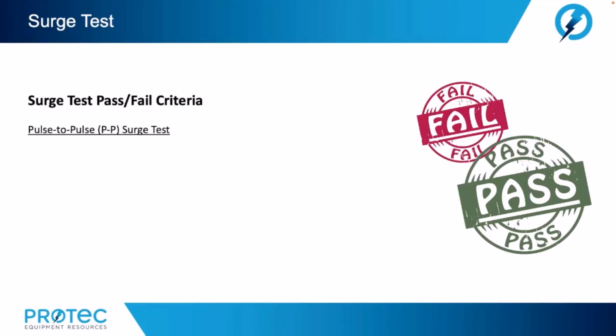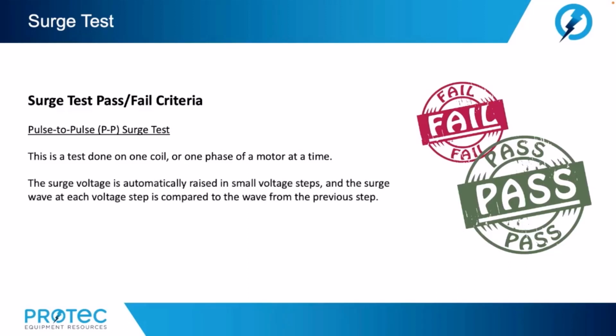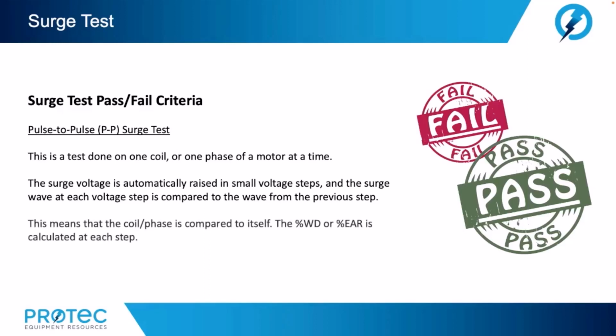Pulse-to-pulse or P2P surge tests. This is a test done on one coil or one phase of a motor at a time. The surge voltage is automatically raised in small voltage steps, and the surge wave at each voltage step is compared to the wave from the previous step. This means that the coil phase is compared to itself. The percent WD or percent EAR is calculated at each step.